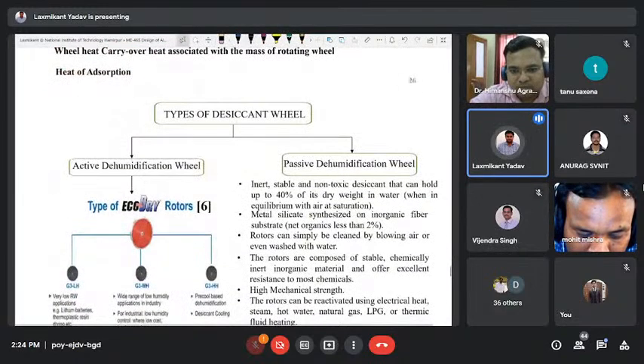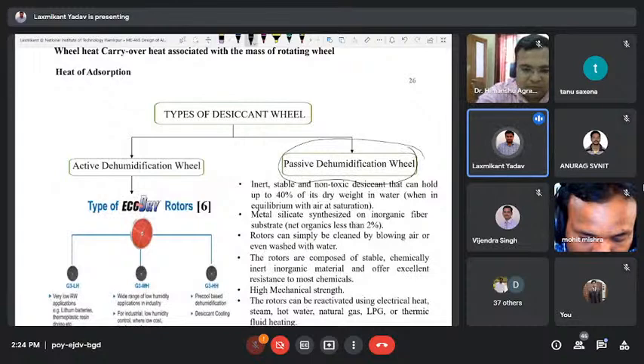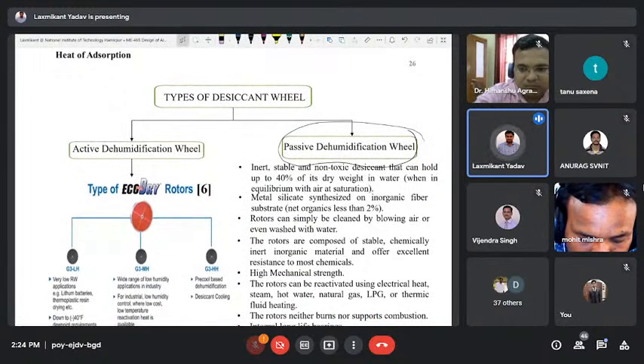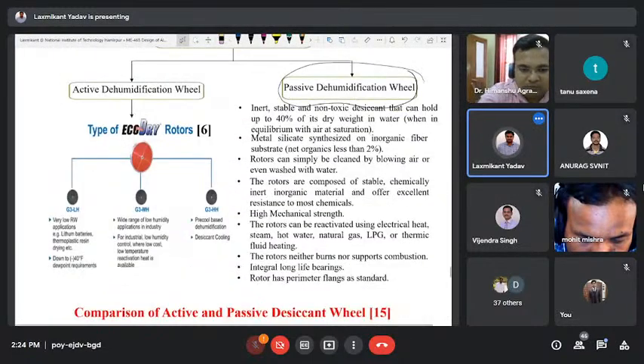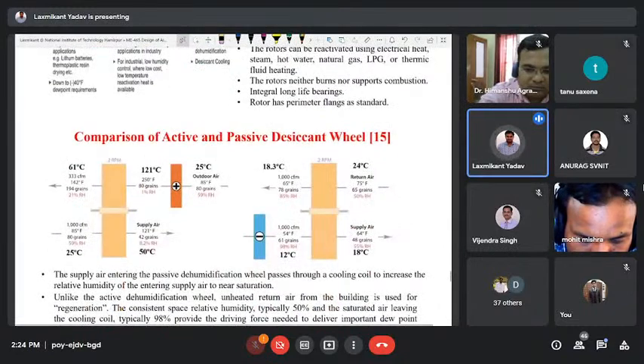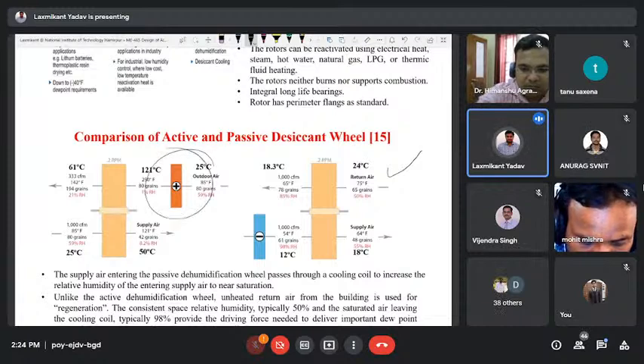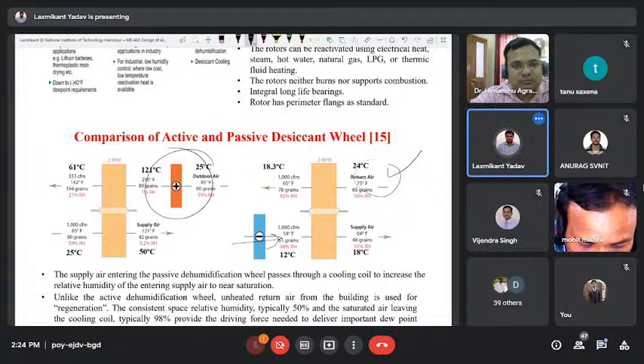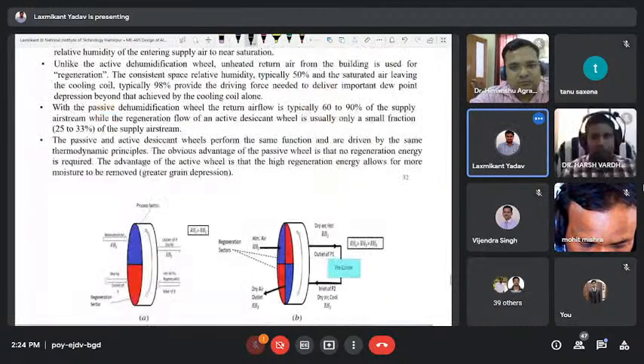Okay. Another wheel is the passive desiccant wheel. The passive desiccant wheel does not require hot air for regeneration. So this is one of the emerging areas. We can also do research on the passive desiccant wheel. In the active wheel we require hot air. However, in the passive wheel we don't require hot air. We pre-cool the air before the desiccant wheel. So this is the emerging area.